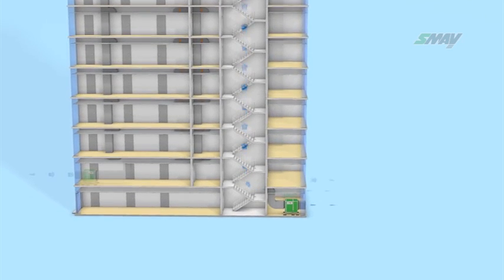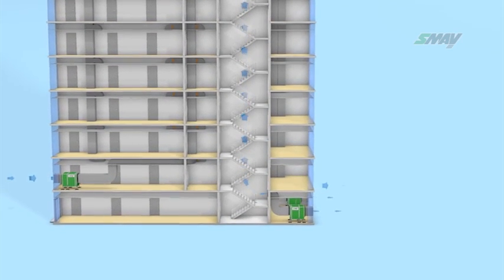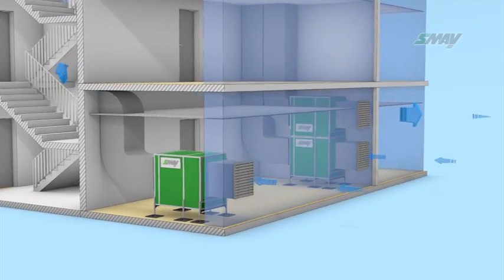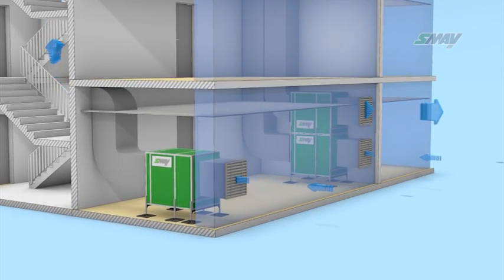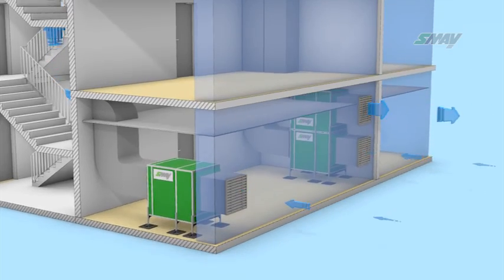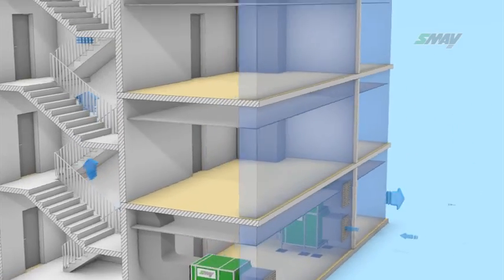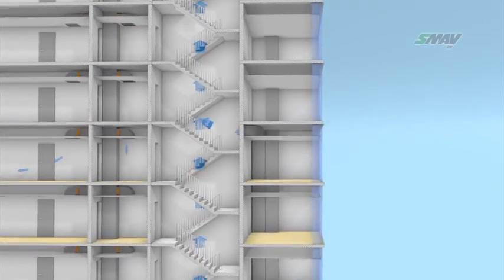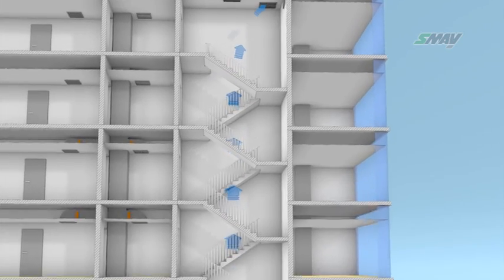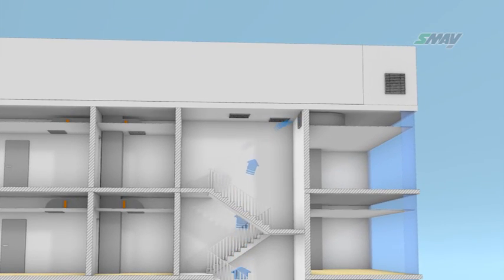Locating all units in the lower floors of the building is optimal since it significantly reduces the risk of sucking smoke from outside. However, if this is not possible, it is allowed to install the units at the roof, but in such case it is recommended to provide a twin air intake system.